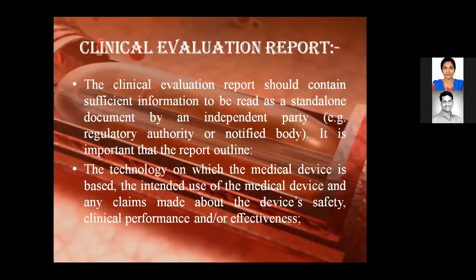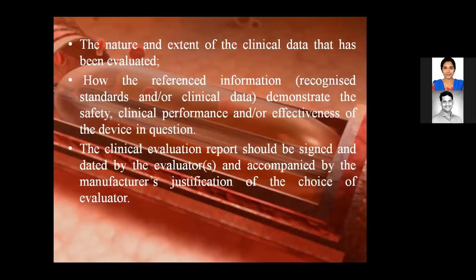Clinical evaluation reports should contain sufficient information to be read as a standalone document by an independent party like regulatory authorities and or notified body. It is important that the report outlines the technology on which the medical device is based, the intended use of the medical device, and any claims made about the device safety, clinical performance, or effectiveness. The nature and extent of the clinical data that has been evaluated. How the referenced information demonstrates the safety, clinical performance, and effectiveness of the device. The clinical evaluation report should be signed and dated by the evaluator and accompanied by the manufacturer's justification of the choice of the evaluator. Just take a look at this video.